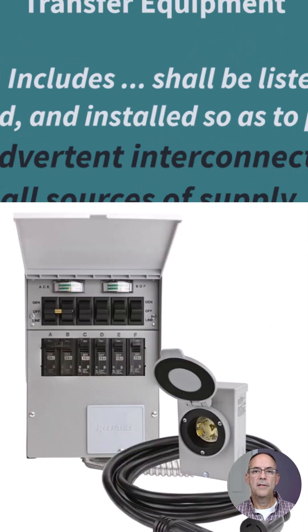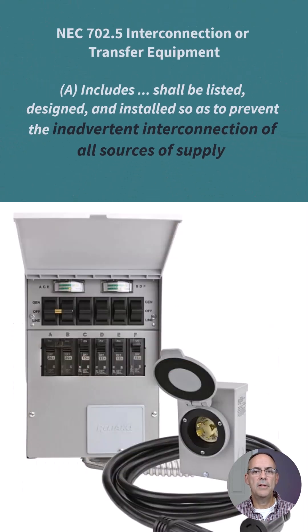This next slide shows NEC's requirement for transfer switches. NEC 702.5 states that the equipment shall be listed, designed, and installed so as to prevent the inadvertent interconnection of all sources of supply. What the NEC is telling us is that this transfer switch must be listed and operate so that there would never be an interconnection between generator power and utility power at the same time.